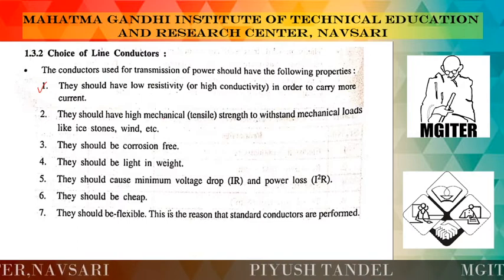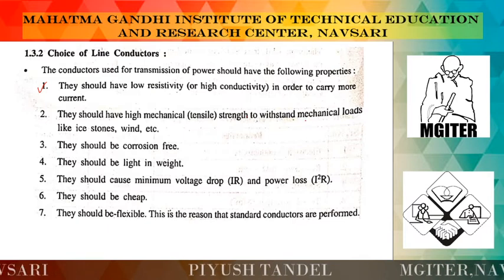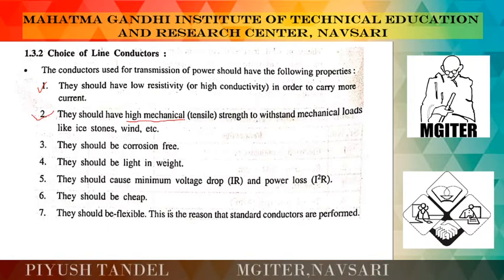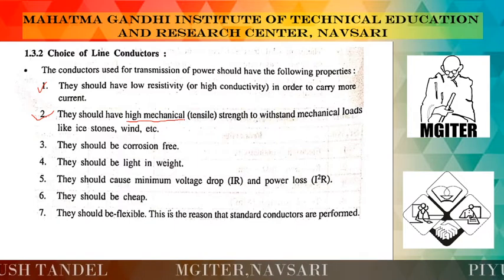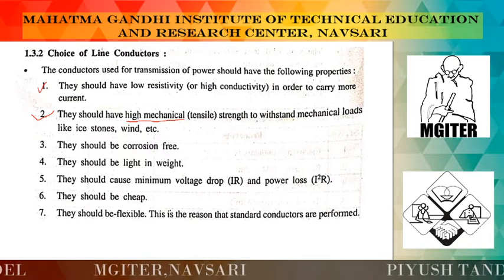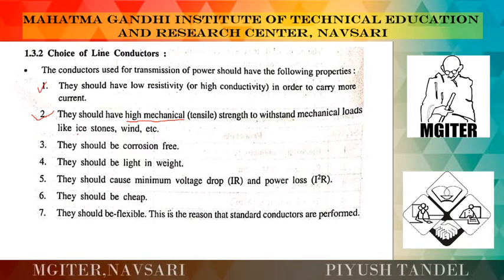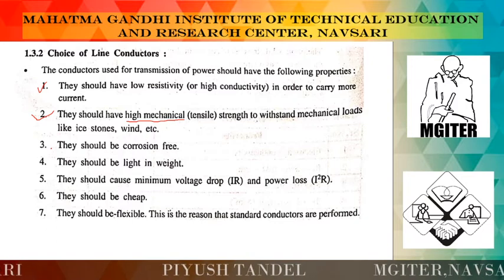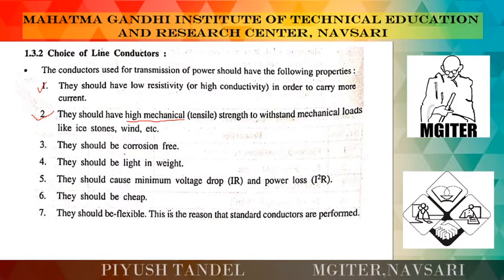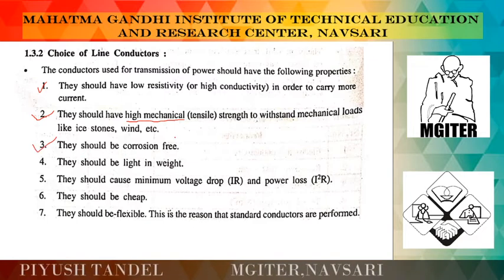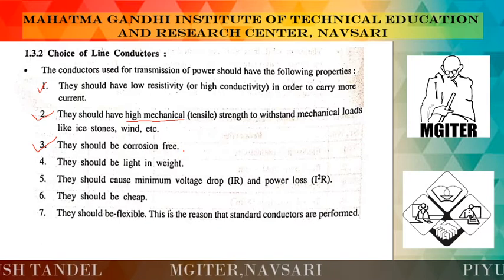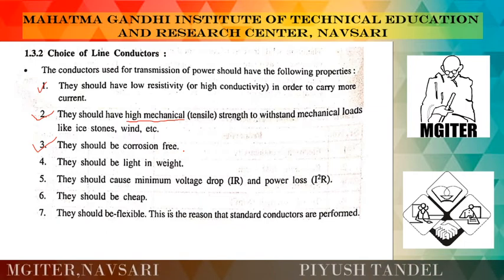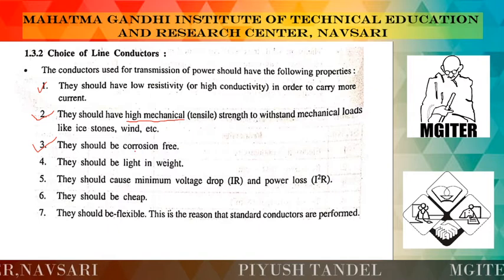Second, they should have high mechanical strength to withstand mechanical loads like ice, storms, and wind pressure. Conductors sag between two different poles, so they need sufficient mechanical strength to withstand ice that forms on the conductor or any kind of wind pressure. Next, they should be corrosion-free — no corrosion or seasonal corrosion effect. Due to different seasons, the conductor should not catch corrosion because if it does, the resistivity of the conductor increases, which is bad for current flow.